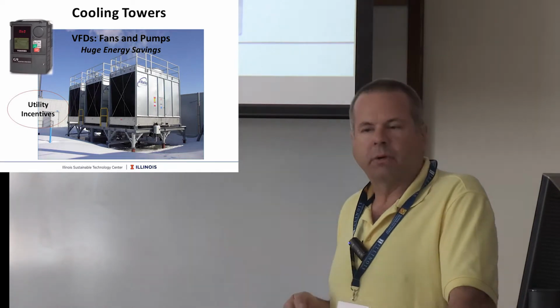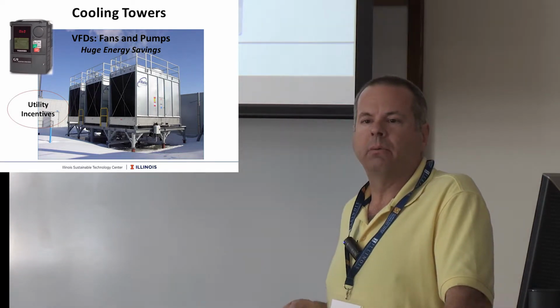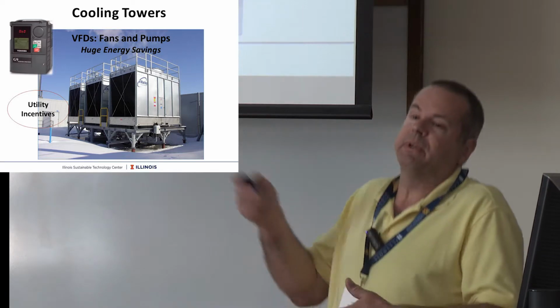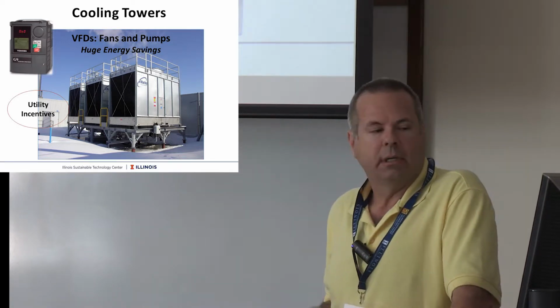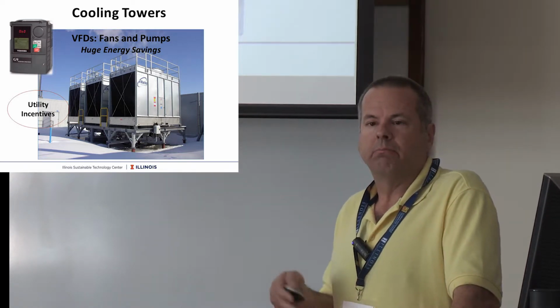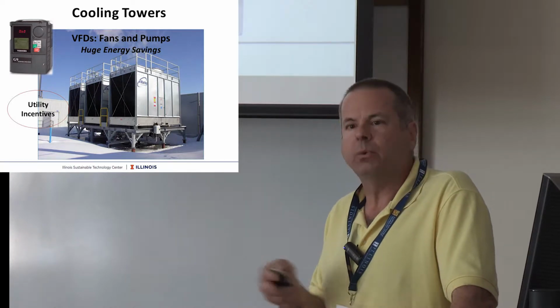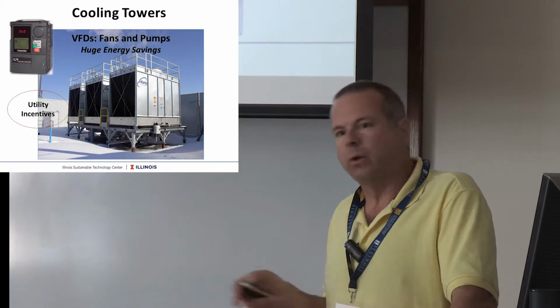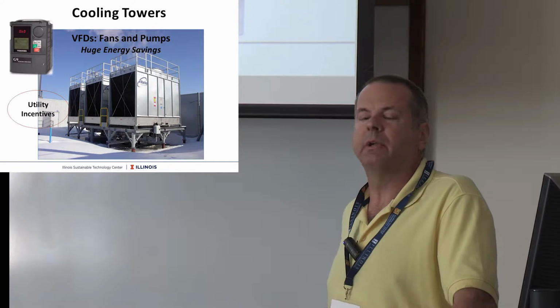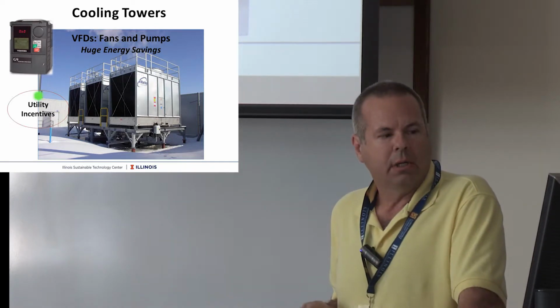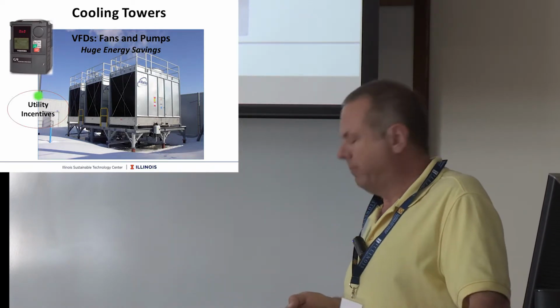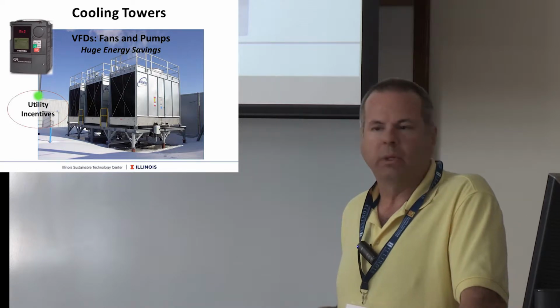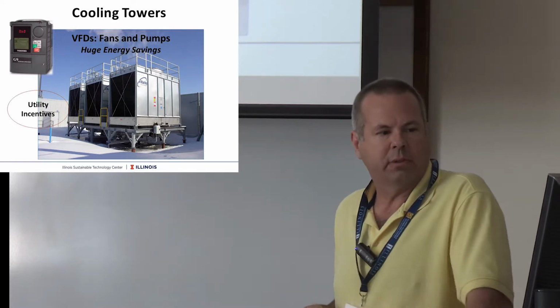Variable frequency drives are great opportunities to add an infinite number of fan speeds and motor combinations. So you may be running two at half speed. And it also has load balancing capability, so they're not fighting each other, especially if they're going to a common header. Utility incentives are available as well for cooling towers, for VFDs.